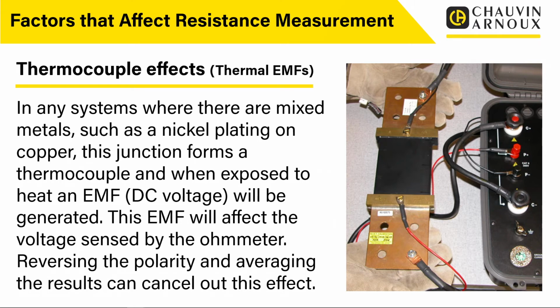Reversing the polarity and averaging the results can cancel out this effect. Because we've got a DC voltage being created, it will effectively add to the voltage in one direction and subtract from the voltage in the other direction. Now, if we're sensing the voltage to measure the resistance, we measure with positive and negative one way round, and then we automatically switch round and measure the polarity in the opposite direction. What that does is it gives us 2 readings. In the first reading, maybe the EMF will add to our reading, and in the second reading, it will take away. So if we average those 2 values, effectively what's in the middle is the true value with the EMF due to the thermocouple effect cancelled out.